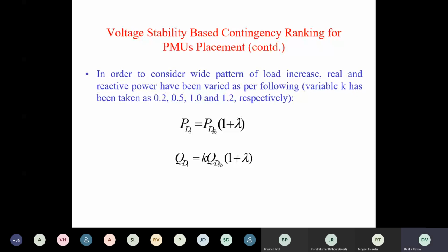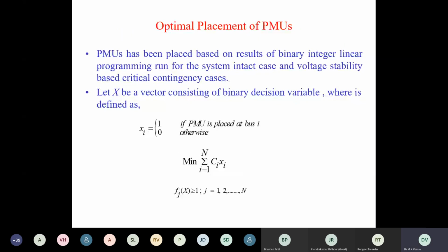He considered the change in real power demand and reactive power demand like this. PDI is PDI base times (1 plus lambda), where lambda is the loading factor, and QDI was considered as K times QDI base. K is used to change the pattern of the load variation. So we consider K as 0.2, 0.5, 1, 1.2. So different patterns of load variations he considered, and for that he considered placement of PMUs.